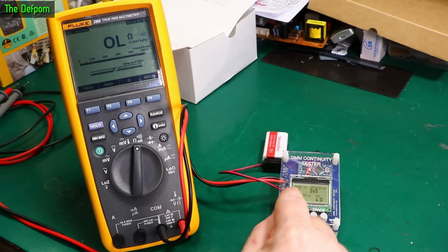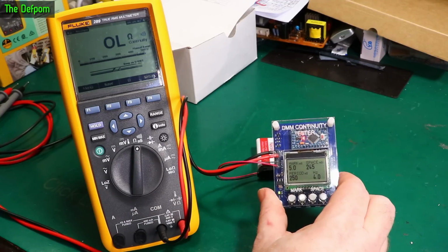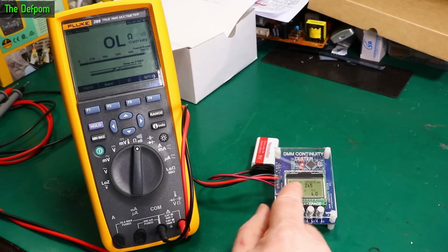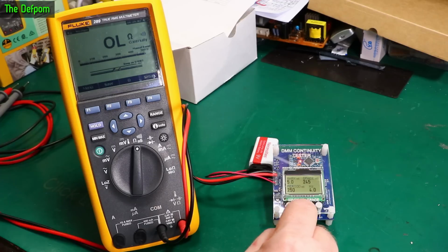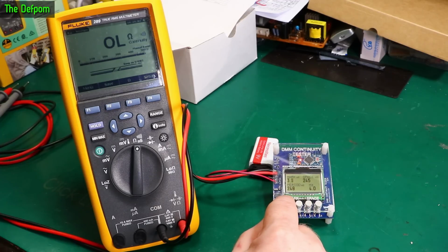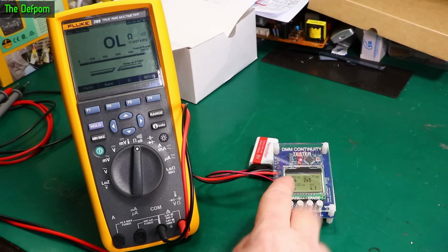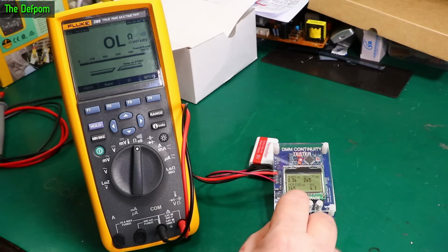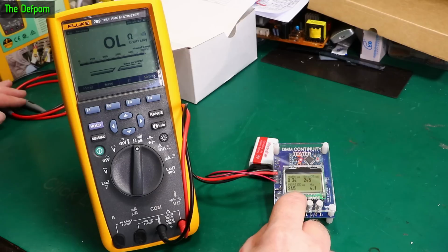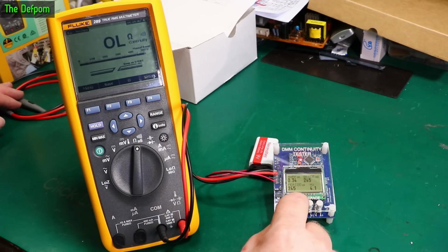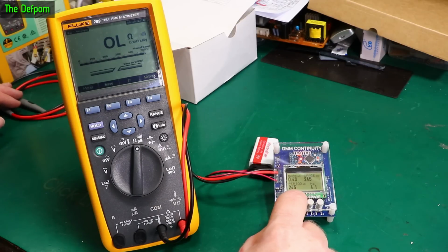So this tests the pulse time stuff available for the meter. You've got a mark space ratio - mark is the on time, space is the time between pulses. I'm going to turn this down like I've just done until I find where the meter no longer responds to those trigger events. Basically what it's doing is switching a MOSFET which is shorting across the leads here. So we'll keep going up until we find it.